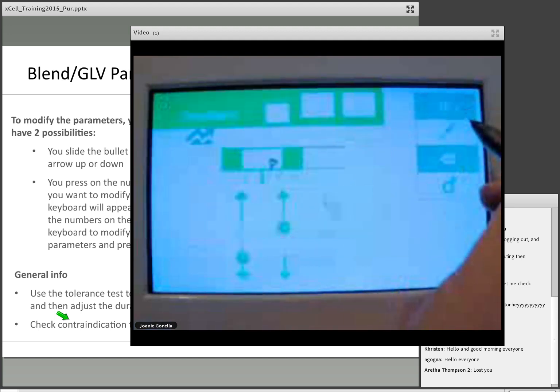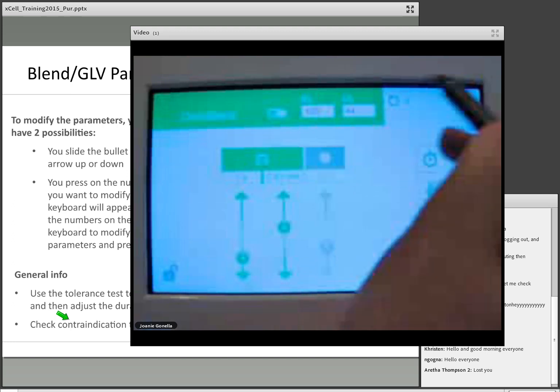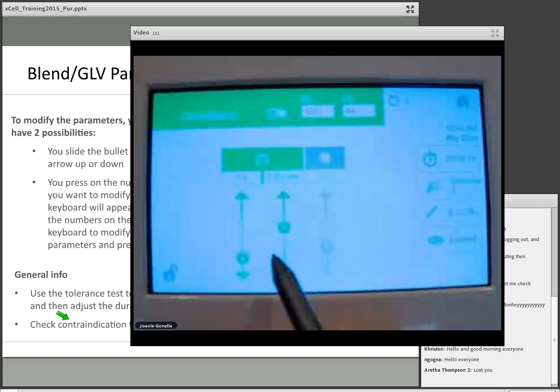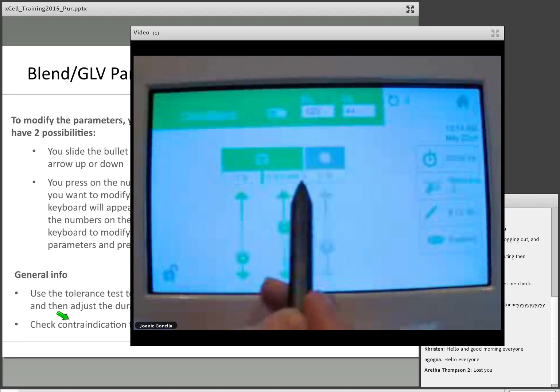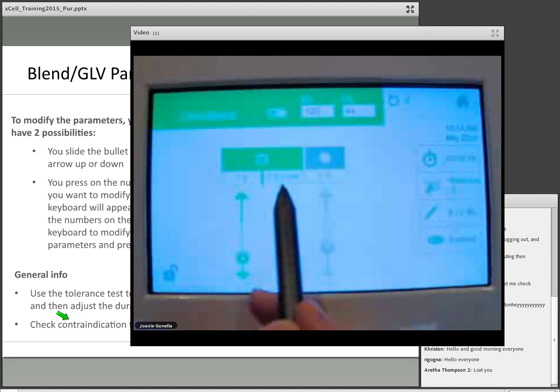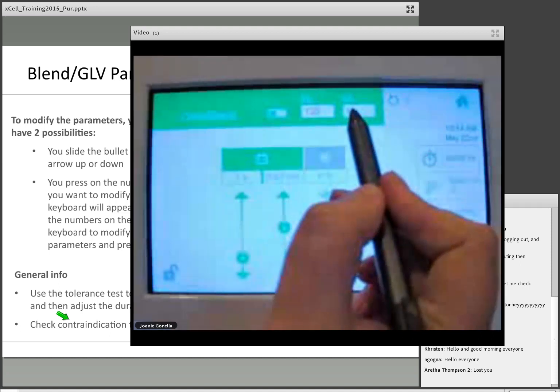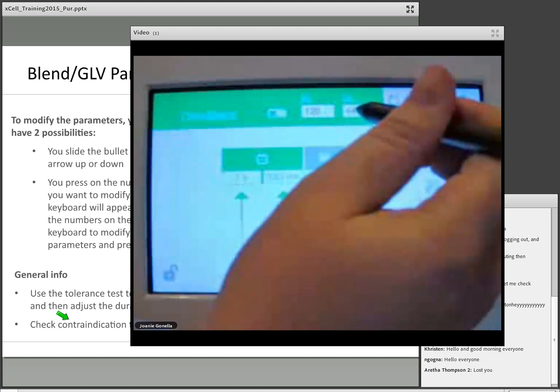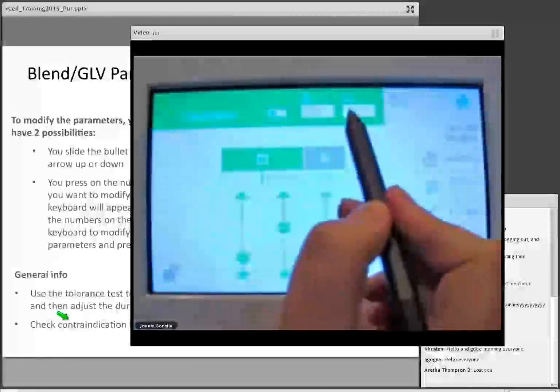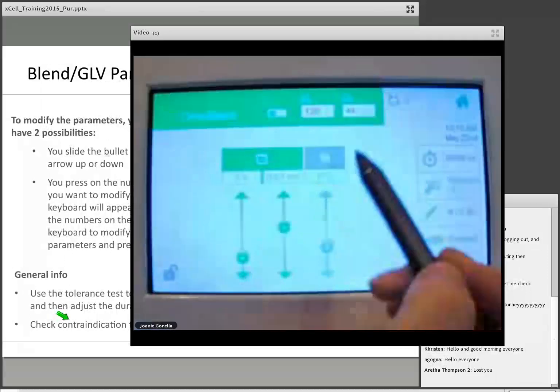I'll go back into my presets, or my treatment screen, I should say. The machine already plugged in that number. So this says 0.63. I know you can't see it too well, but it's the number I just tested for. The machine will then also calculate units of lye for you. So this is 44 units of lye. This is another thing we'll have to fix. On a future update, I would like this to be interactive, so I can actually put in my units of lye up here.